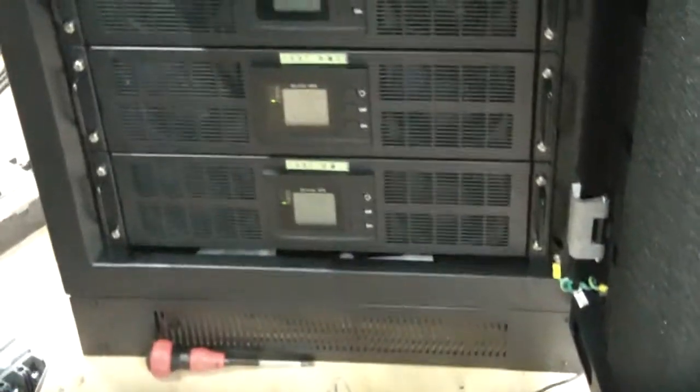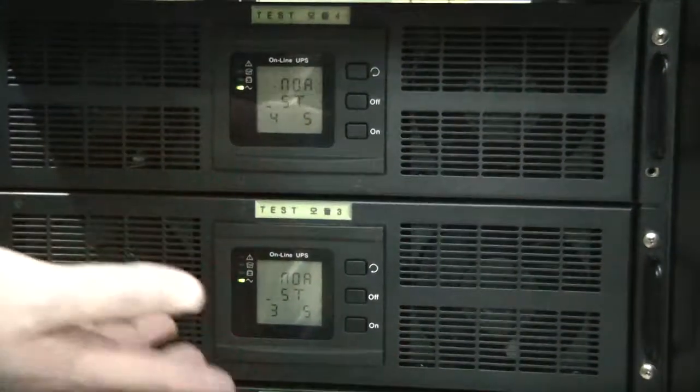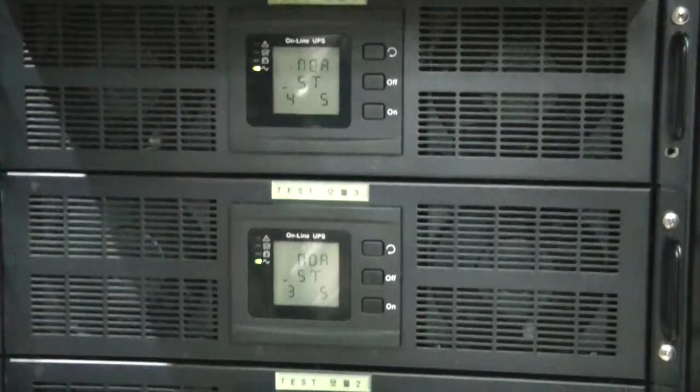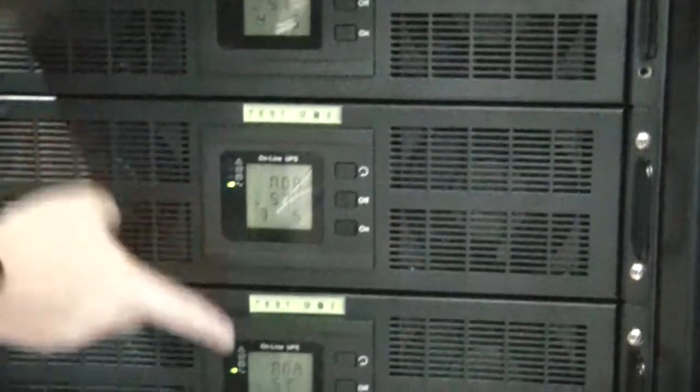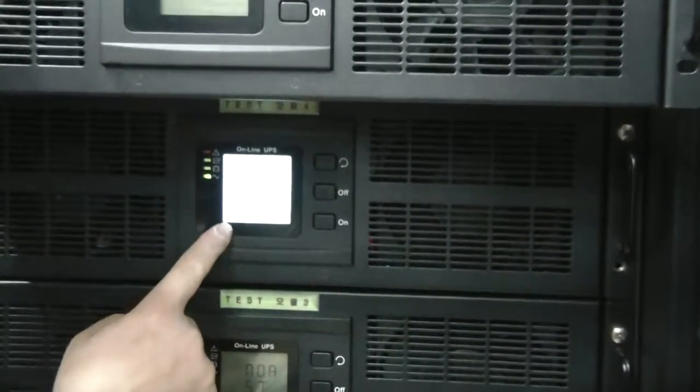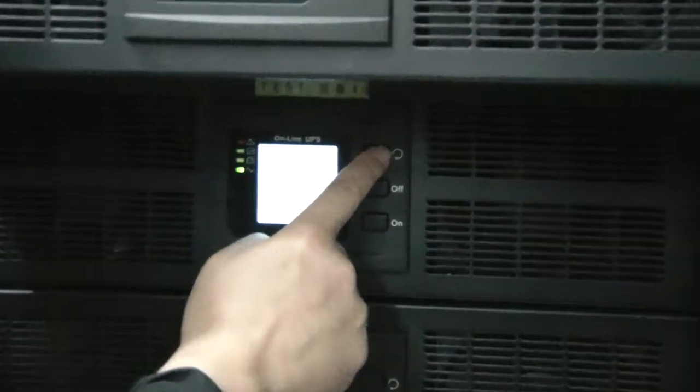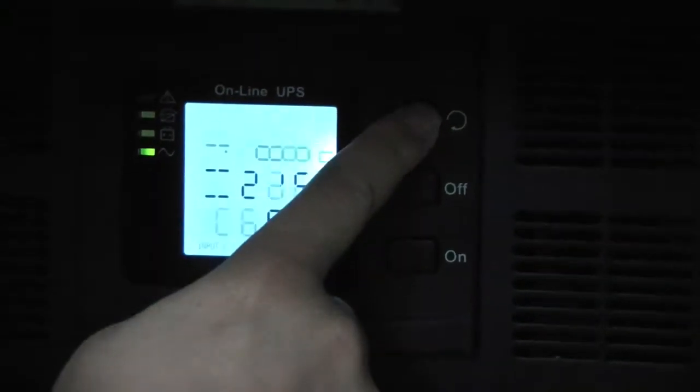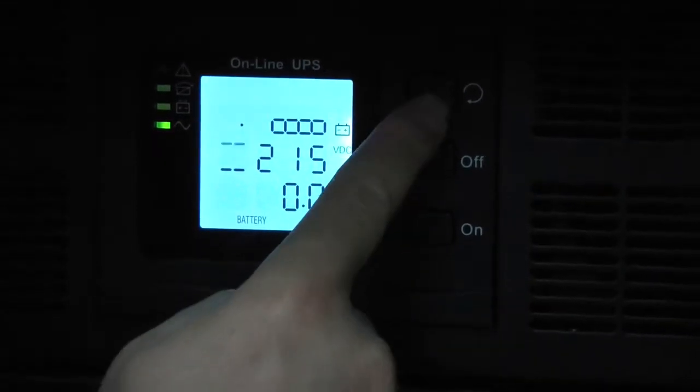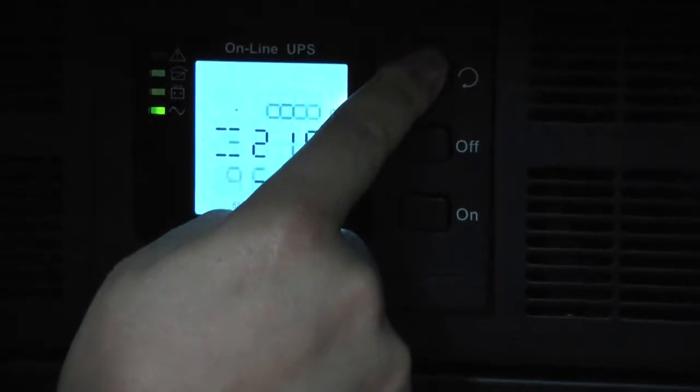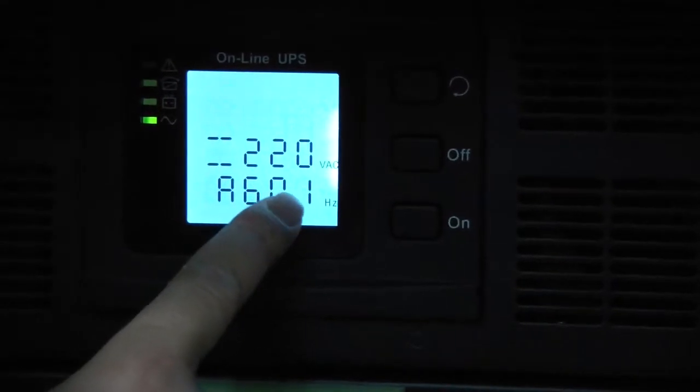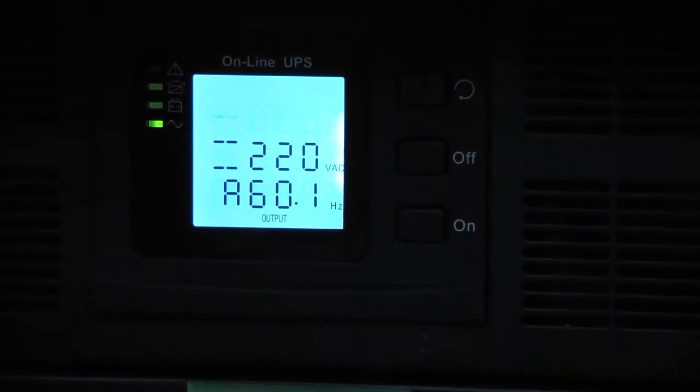But you can see, without the module, the other modules are still alive, still supplying power to the load. Input is 221, 222. Battery is 215. Output load is 220. So this is right.